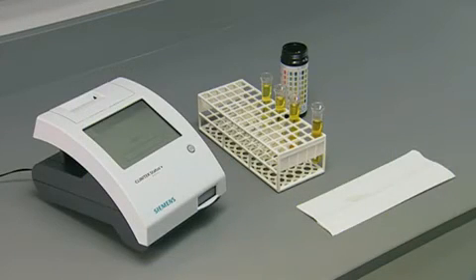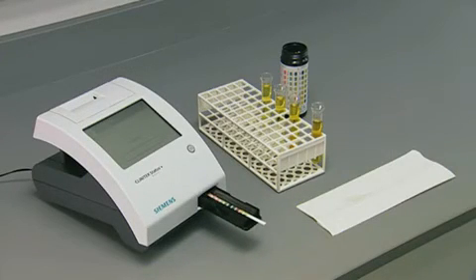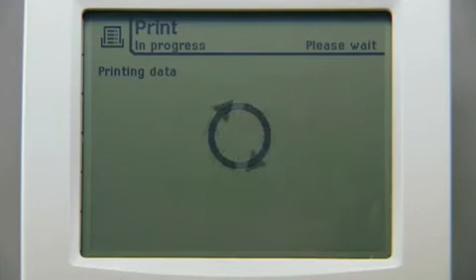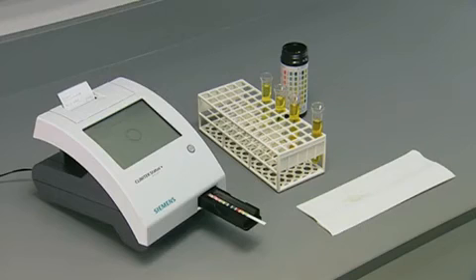When analysis is completed the test strip is ejected and the results can be reviewed on screen or on a printout. If the analyzer has been set up to print the results automatically the printing screen displays until the printout is completed.